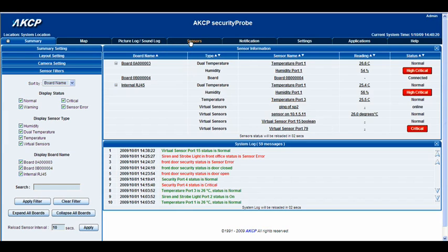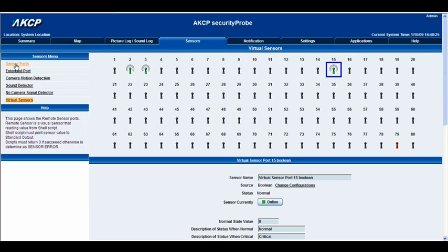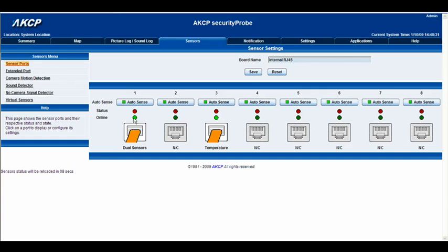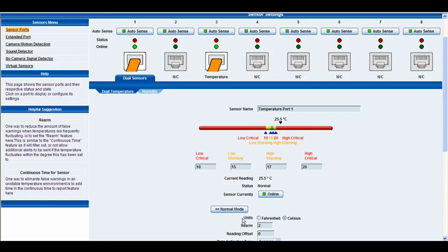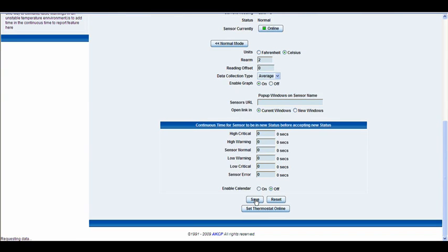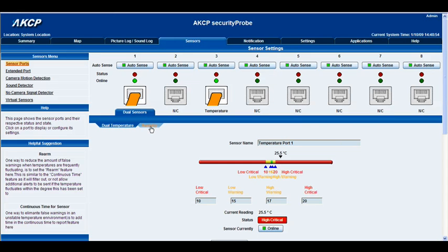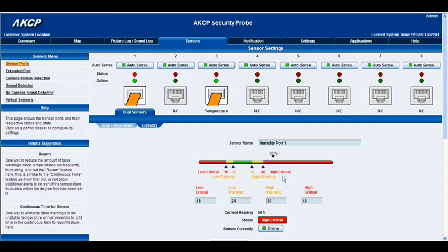Let's get back to our sensors, go to our sensor ports, and go to our dual sensors. First of all let's take our temperature into a high critical and save that. Now let's click our humidity tab. As you can see our humidity is already in a high critical. The boolean virtual sensor isn't going to revert to a high critical status until both of these are in high critical.